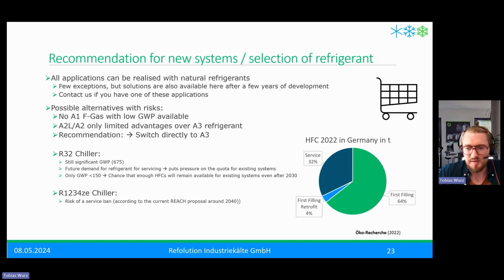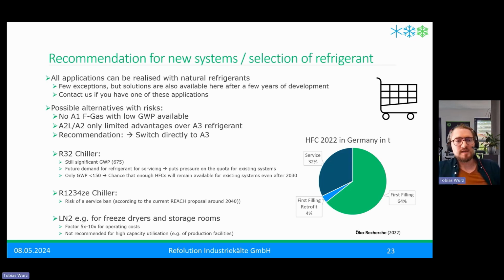but yeah, it's a risk you have to calculate in your decision. And as I said, LN2 could be an option if you have low operating time. We say don't use LN2 otherwise, because we estimate a factor of 5 to 10 times for operating costs if you use LN2 in comparison with, for example, a butane cascade or air as refrigerant.